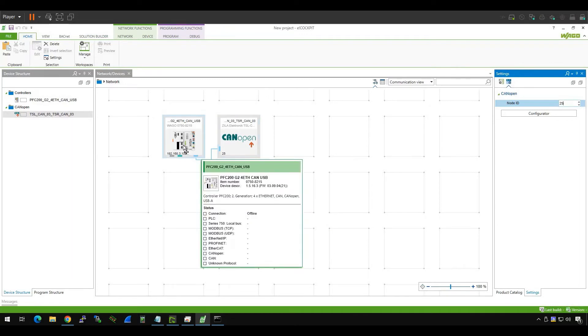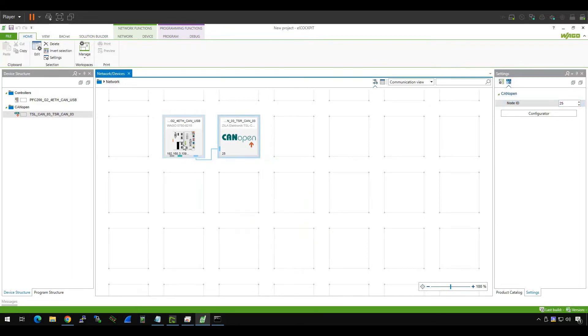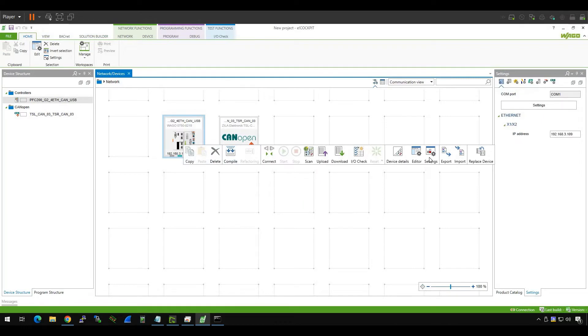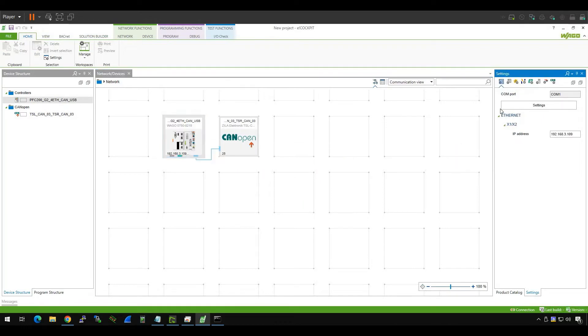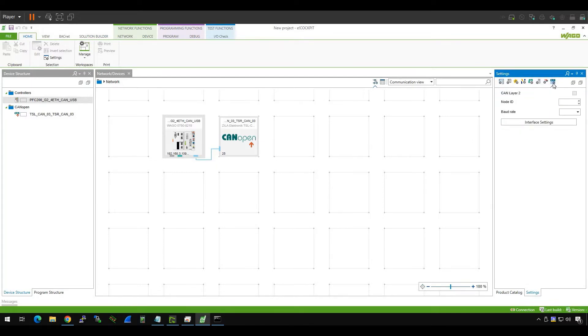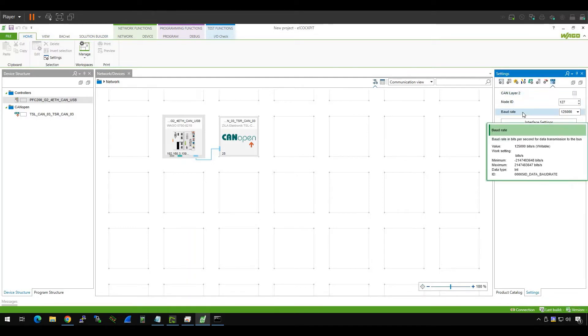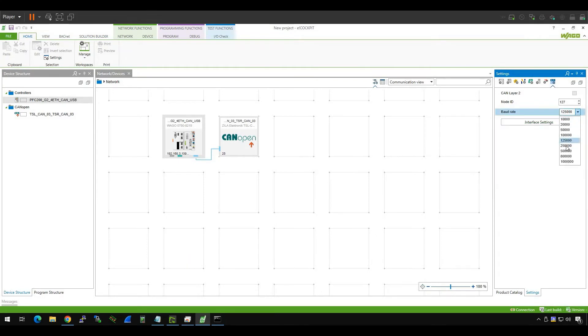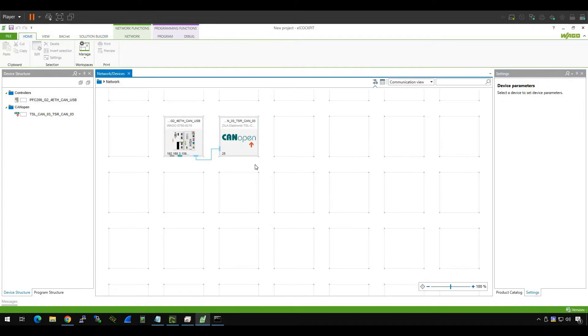Then we need to set the master side. Do the same one. Select it, right click, settings. And go to the right hand side, the settings screen. Go to the CANopen icon. Then here, there's the baud rate. You need to take care about it. In my case, I'm using 250k. So choose 250k. Finish. Okay. Now the network config is finished.